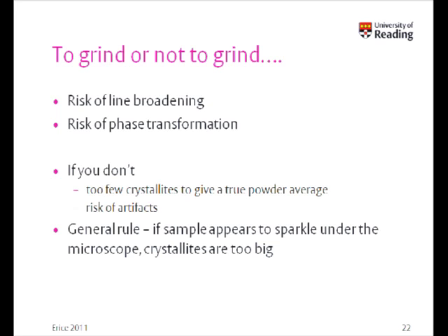Okay, to grind or not to grind, that is the question. If you're given a sample and it looks rather sticky or the crystallites look a little bit large, then there's a strong temptation or clear benefits to reducing the particle size. The benefits are that the smaller your particles are, the more representative sample you'll have in your beam, you'll get proper powder averaging. The main risk that you run is that of inducing a phase transformation due to pressure or temperature effects. Of course, you're likely to induce some line broadening, but that may not be that important if the resolution of your instrument is limited anyway.